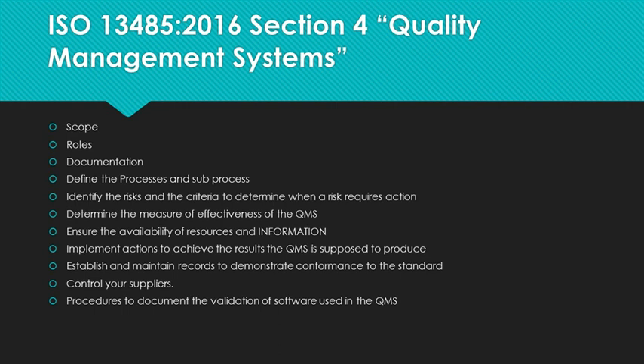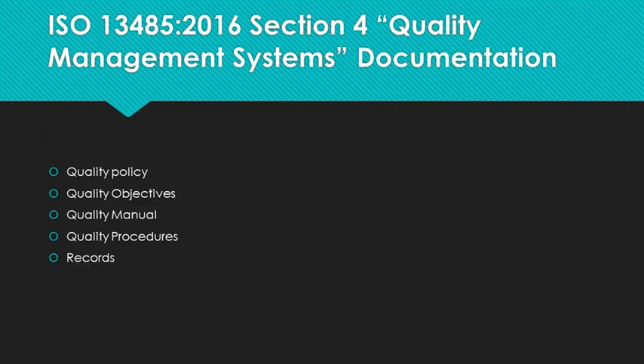Most auditors, but not all, agree on this. The only software used to test the effectiveness and conformance of the product needs to be validated. If you do not have a registrar, this is a very important question to ask when selecting your registrar, because validation is a very expensive process. That summarizes the big decisions that need to be made just to develop the quality management system.